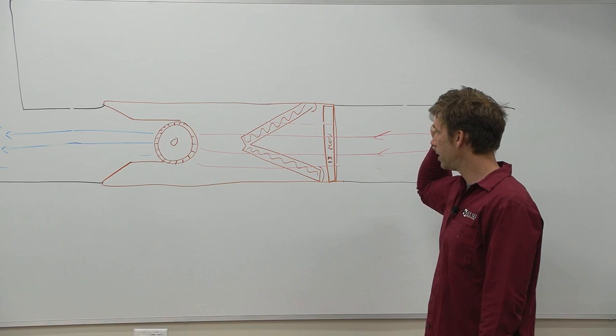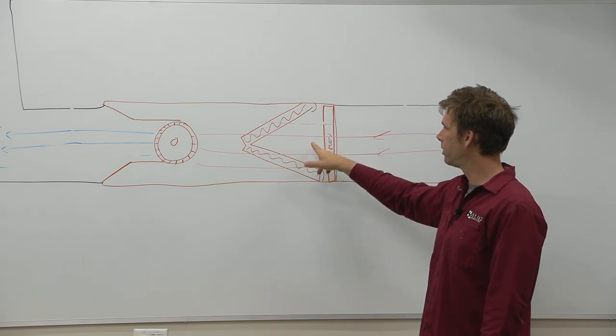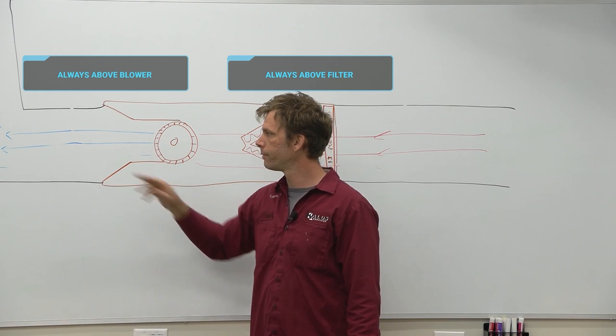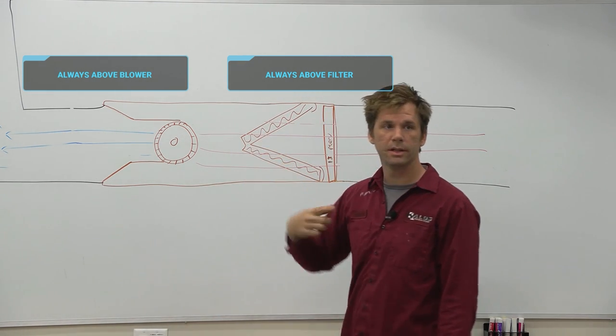You'll get a false low in that you're looking at your numbers and you're like, I have 0.2, that's great, there's not much resistance for my system, it's not working too hard. I must have the airflow that I need. When in reality, you're just measuring at the wrong place.